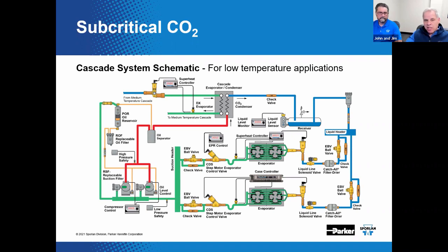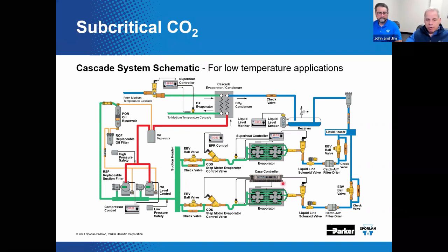The receiver feeds liquid to the electrically actuated, electronically controlled expansion valve, which are told what to do by superheat controllers or case controllers. These controllers either control the superheat of the evaporator coil or the discharge air temperature of the display case, or maybe even both.